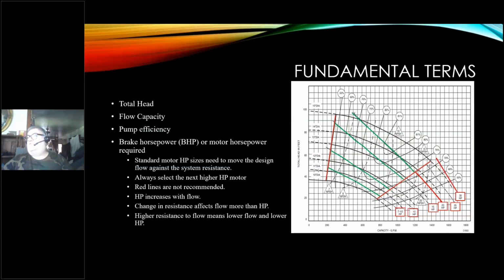Again, at the 20 horsepower, or the 30 horsepower, sorry, 30 horsepower doesn't even meet the curve. Same thing with the 25 horsepower. In this case, we would not be able to operate on this family of curves, even though the top one says that we can operate in there. It does not recommend it. Okay, so this is getting pretty narrow as far as our application goes. Again, all of these red lines, don't select it.